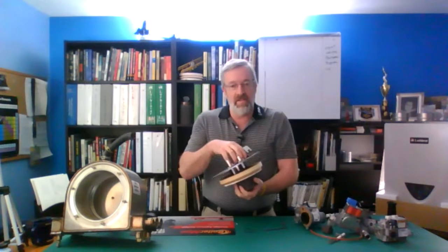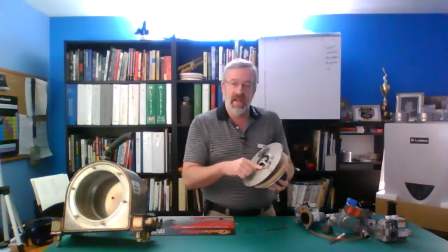Let's see. So a PM. I'm going to replace the igniter and flame sensor. I'm going to replace my gaskets, potentially on the older style fire tube. I'm going to have to put a new gasket on there. A lot of times I'll leave the fan on top. That prevents you from replacing this fan gasket. But if you take the fan off, you will need to replace the fan gasket. So it's a pretty good idea to have with you a heat exchanger door gasket, fan gasket, an igniter and flame sensor if you're going out to do a PM on one of these.